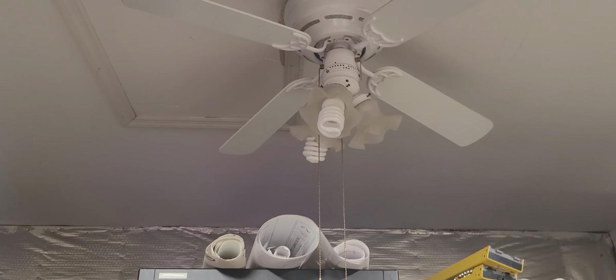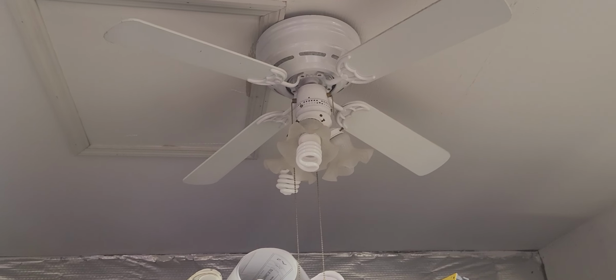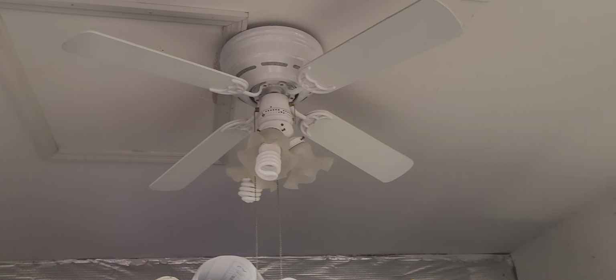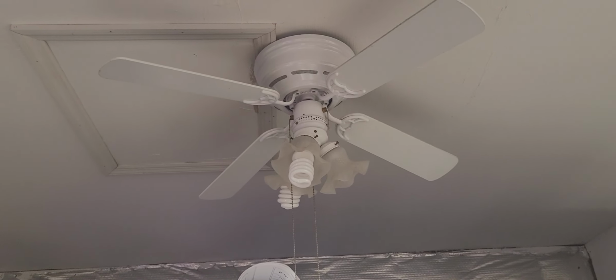Do not have a ceiling fan in your IT environment because it doesn't actually give you cooling power. It just pushes the heat around, and that motor up there is going to make more heat. So I only use the fan when I'm not running my racks because I don't want to exacerbate the heat up there down here in this environment.